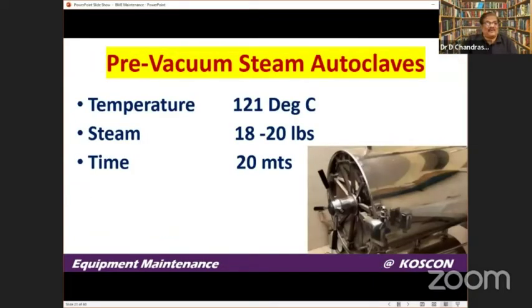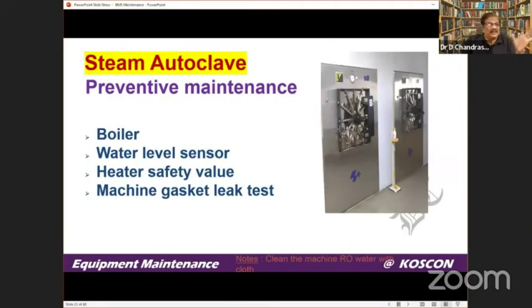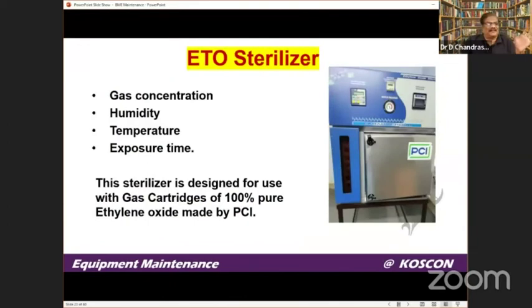For pre-steam, pre-vacuum autoclaves, we don't use the vertical autoclave because it does not have a vacuum cycle. The known parameters are 120 degree temperature, steam of 18 to 20 lbs, and time of 20 minutes. You need to check the boiler, water level sensor, heater safety valve, and machine gasket leak test, all as part of periodic maintenance.